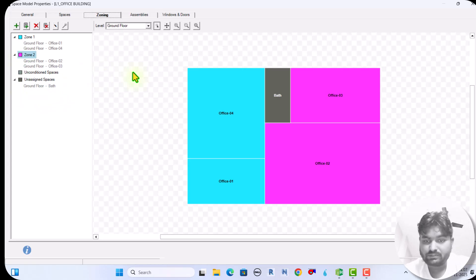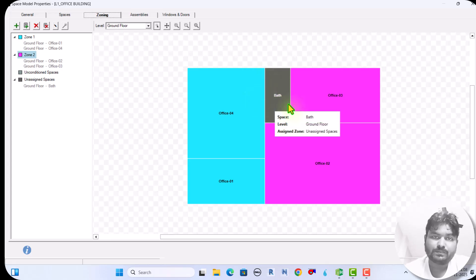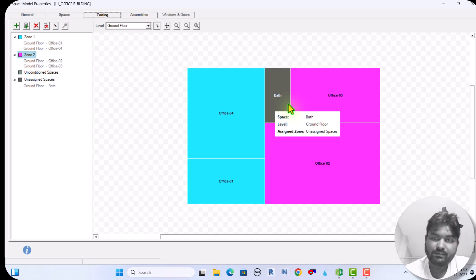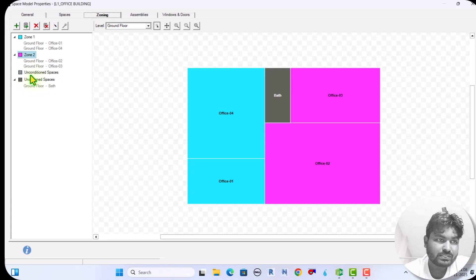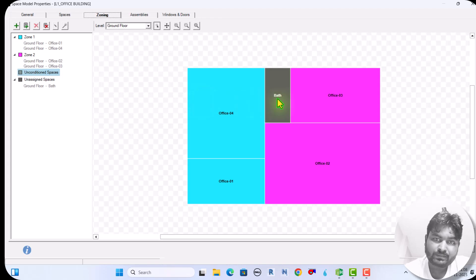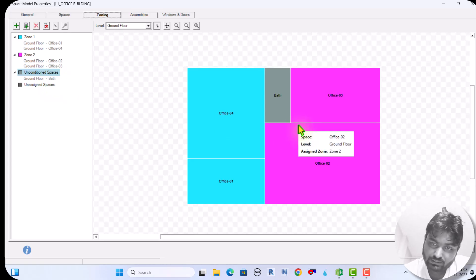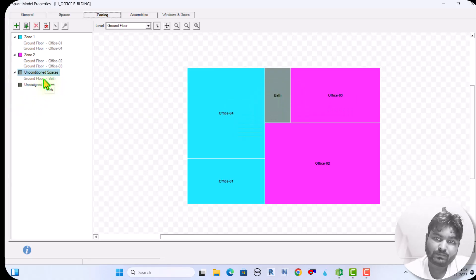The only unassigned space remaining is the bathroom. If I generate the report with an unassigned space, an error message will appear. Even though I am not going to install an AC machine in the bathroom, I still have to assign it to a zone — as an unconditioned space. I click 'unconditioned space' and assign the bathroom. Any space where no AC machine will be installed must be treated as an unconditioned space.